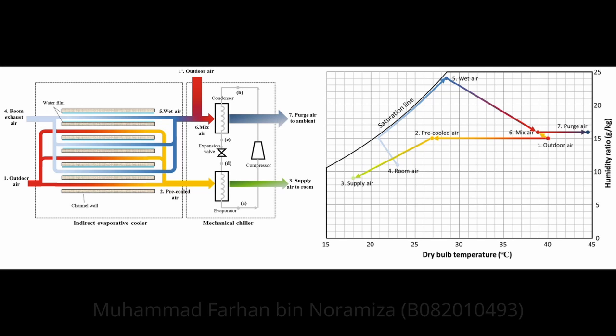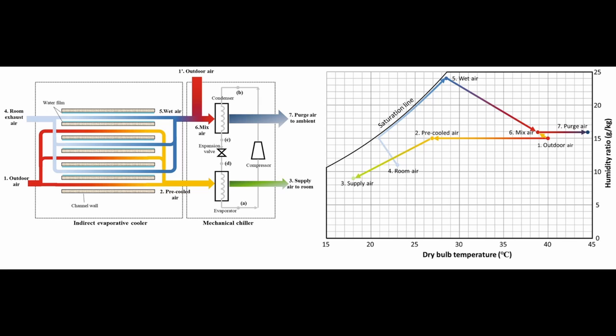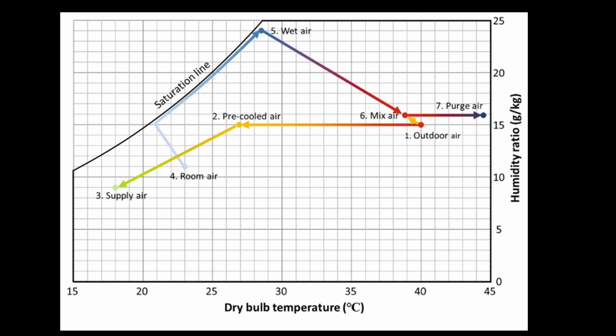I'm going to explain the diagram and illustration. On the left, we can see the schematic of the combined IEC MVC system. On the right is the process demonstration in the psychrometric chart. Usually, a psychrometric chart has more elements than this, but we only have 3 elements, which are saturation line, dry bulb temperature, and humidity ratio.